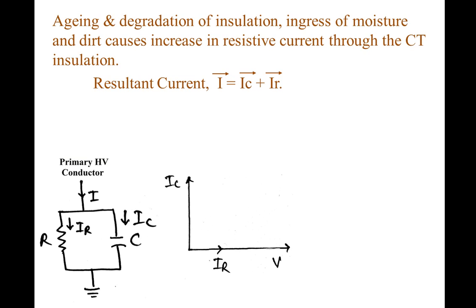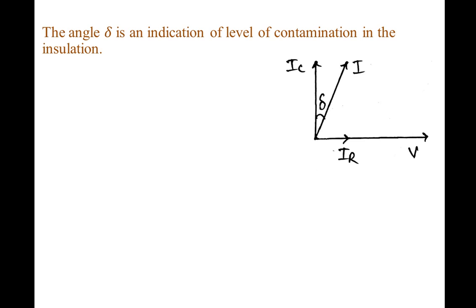The resultant current I will be equal to the vector sum of IC and IR. Therefore, the resultant phase shift between the applied voltage and total current will be less than 90 degrees. The angle between the capacitive current and the total current is called delta. The angle delta indicates the level of contamination in the insulation, and is also called as the loss angle.